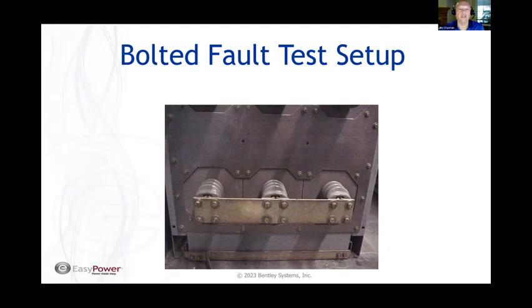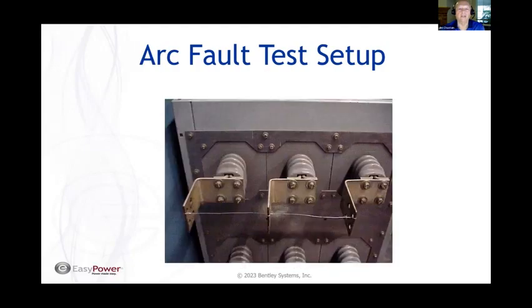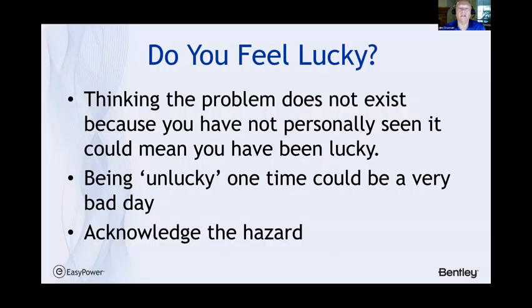Now, when it comes time to do an arc flash test, this is what the fixture looks like. And this little 12 gauge wire that's strung from the different contacts vaporizes when the current is turned on and creates the plasma ball. As long as that plasma can touch the electrified buswork, the arc itself will propagate from wherever it started to a full-blown three-phase fault. It literally takes 30 milliseconds or less, even if you just try to fault one bus. So the body of knowledge of arc flash features and characteristics is growing. The problem is not thinking that it doesn't exist because you haven't seen it. It may be that you were just lucky during that time, and all you have to do is be unlucky one time to have a very bad day. So acknowledging the hazard is the first step.